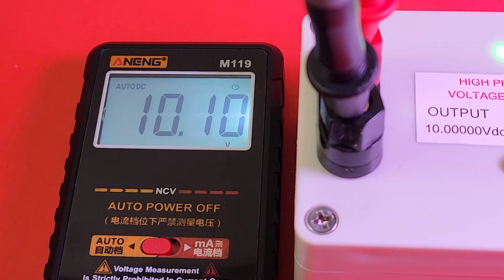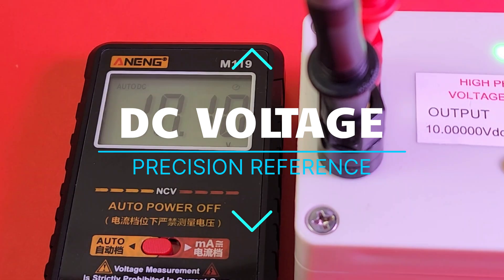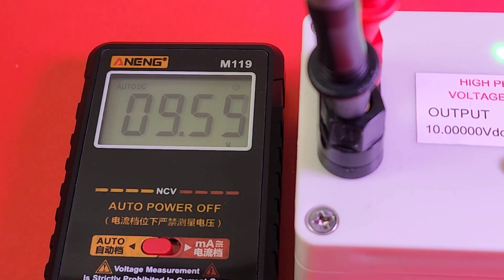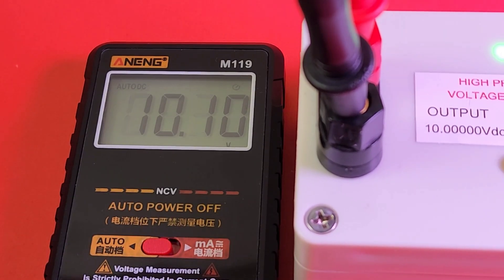Looking for 10.00 volts - coming in at 10.10. According to the specs, this is plus or minus five digits and 0.3%. So we're a tad off, ANENG.